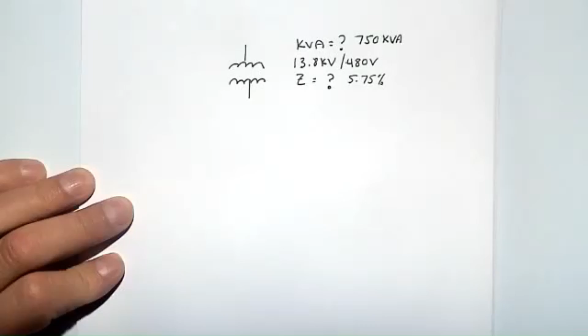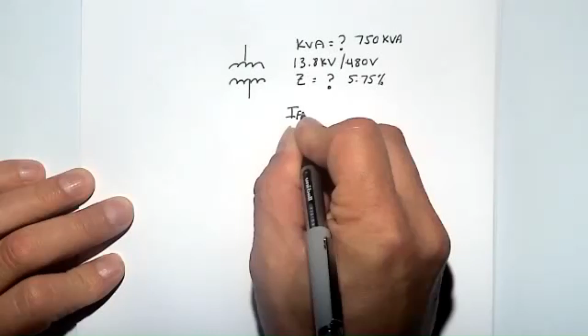So for medium size and smaller dry type transformers, if you don't know, you can use that number, but again, using a bigger number gives you less fault current. So we want to be careful we're not overestimating impedance. For this liquid filled transformer, we're going to use 5.75. But anyway, let's say we figure out I full load on the primary is about 31.4 amps.